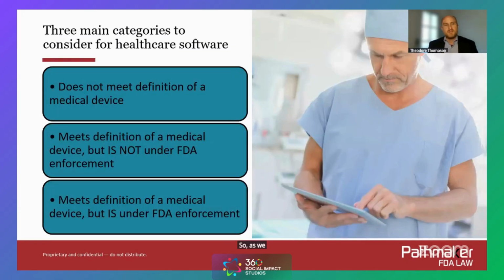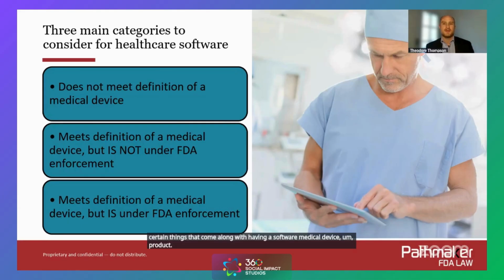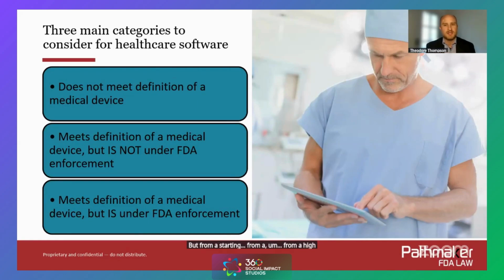So as we mentioned, there's a lot of activity right now in software as a medical device, and there are certain things that come along with having a software medical device product. Not only do you have to consider what category of medical device it is and the specific regulation, but from a high level, it's helpful to understand whether your software meets the definition of a medical device or whether it is not a medical device. If it is not a medical device, then your pathway to market is a lot clearer and a lot less expensive than if you have to go through an FDA submission.